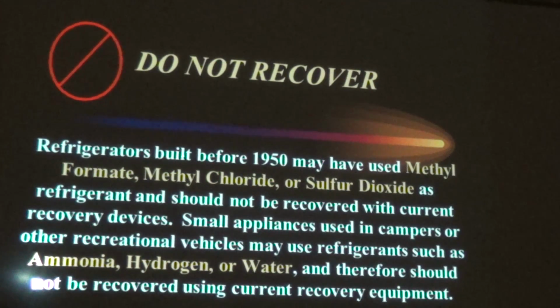Now, this is actually a test question I've seen. Refrigerators built before 1950, good luck finding one, may have used methyl formate, methyl chloride, or sulfur dioxide as the refrigerant, and should not be recovered with your recovery device. Small appliances used in campers or other recreational vehicles may use refrigerants such as ammonia, hydrogen, and water. Therefore, they should not be recovered using current recovery equipment.